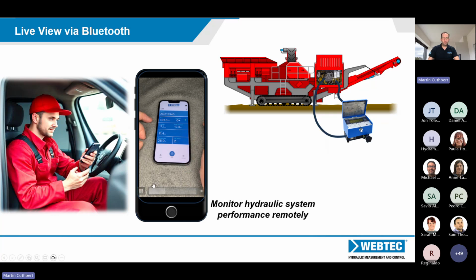Now this is a read-only device. It will not drive the digital hydraulic multimeter, and it will not allow you to record any data. But the benefits are that there could be safety implications where you want to move away from the tester and just use the mobile phone as a readout. There could be adverse weather conditions, so it's raining hard - the digital hydraulic multimeter has a very high IP rating, so rain is not a problem, but it could be for you. So you may want to get inside the cab where you've still got full control of the circuit.